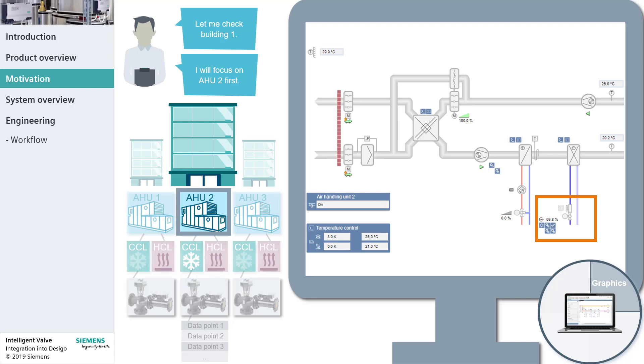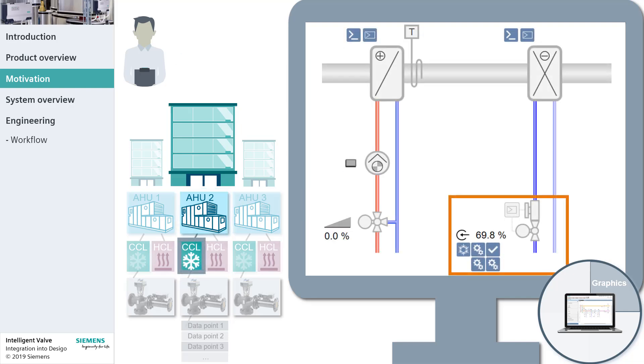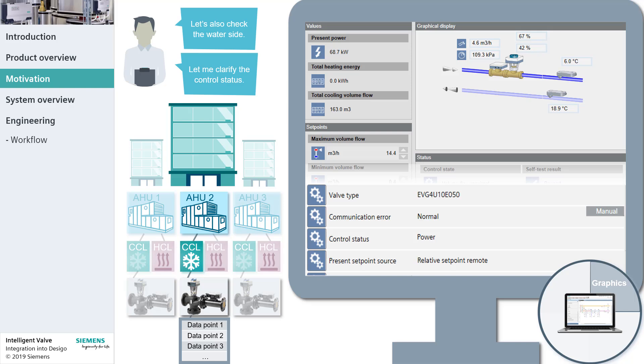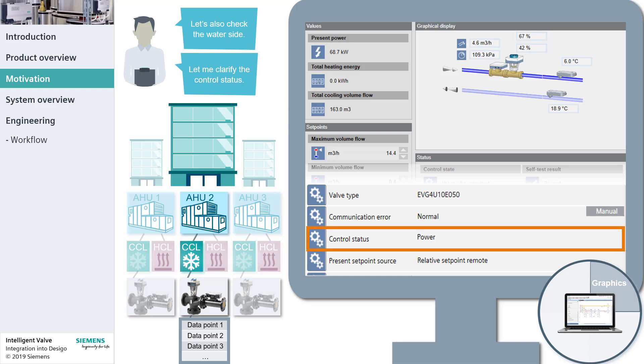So far, everything seems to be okay. Mike navigates to the cooling coil and sees that the cooling circuit is in normal operation. With the intelligent valve integrated into Desigo, Mike can navigate to the field device level to check the current state of the intelligent valve. The graphic shows the volume flow and the supply temperature seems to be okay. Mike can even find more information about the data points in the contextual pane — for example, he can check whether the device is now controlling by position, volume flow, or power.